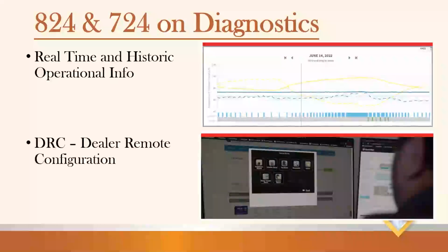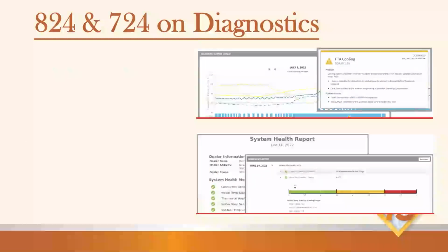Real-time and historic operational info, and that's up to 30 days past. So we can see 30 days of runtime, and you can change settings from there. We at Tech Services cannot change your settings, but you as a dealer can. So that is pretty handy. If you're doing some kind of lockout for dual fuel and you want to make some settings changes, you can do that from your desktop. Don't have to be on site.